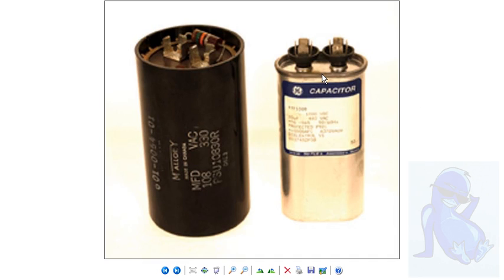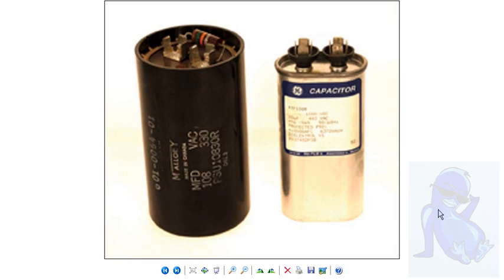And we haven't talked about capacitors yet. There are some videos on capacitors out there. When we get into motors we start talking about capacitors. But basically if you start seeing this swell you need to change it out. This is a start capacitor which is going to be plastic. This is a run capacitor. You may not have a start capacitor. Just a run capacitor.